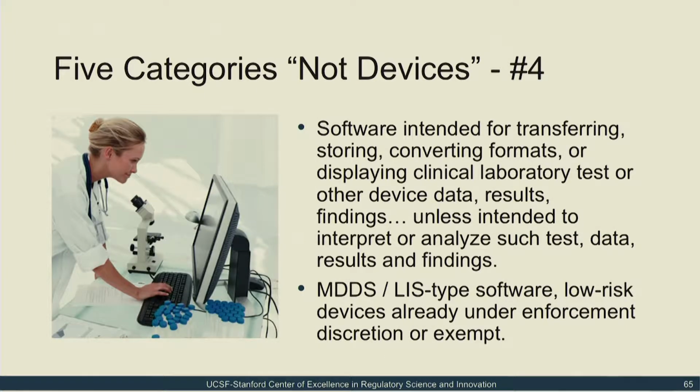The fourth exclusion provided in the Cures Act is software intended for transferring, storing, converting formats, or displaying clinical laboratory tests and other device data and results, findings by the healthcare professional with respect to such data and results, general information about such findings, and general background information about such laboratory tests and other devices, unless the software is intended to interpret or analyze clinical laboratory tests or other device data, results, and findings.